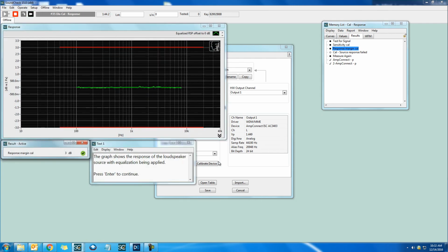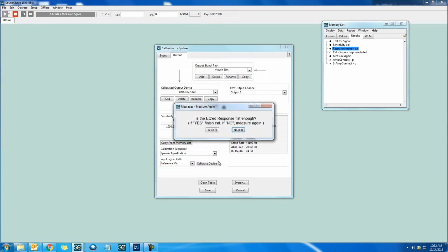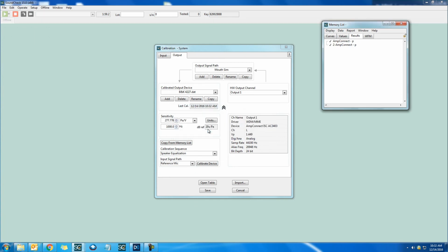And here's the final result. The speaker is very flat, and it took care of a little bit of the half a dB swing that we were seeing in our first equalized run. And then this does look good enough to me, so I'll hit yes. This updates the sensitivity and the date of the calibration of the device. And our mouth simulator is now calibrated and ready to use in a sequence, so we'll hit save.